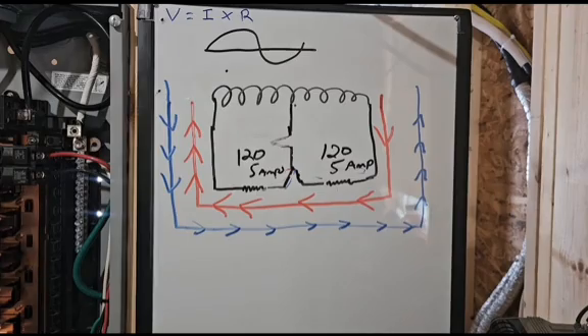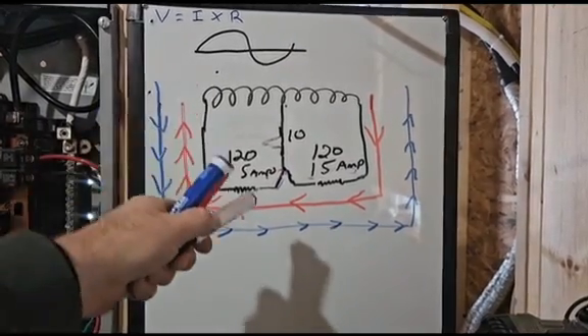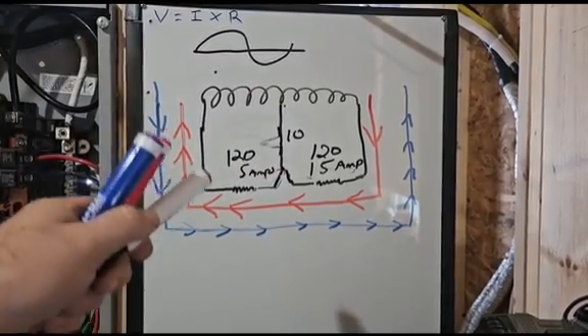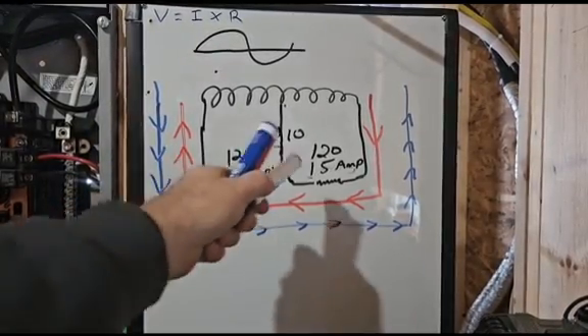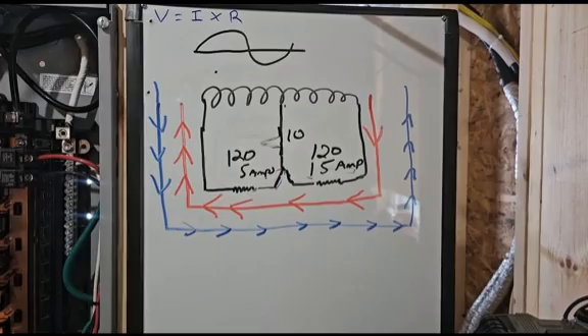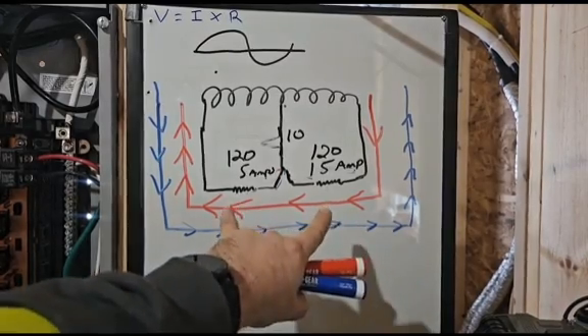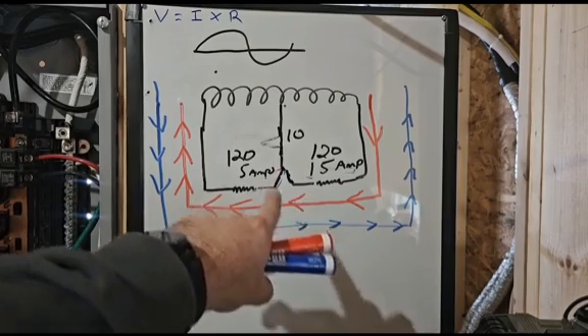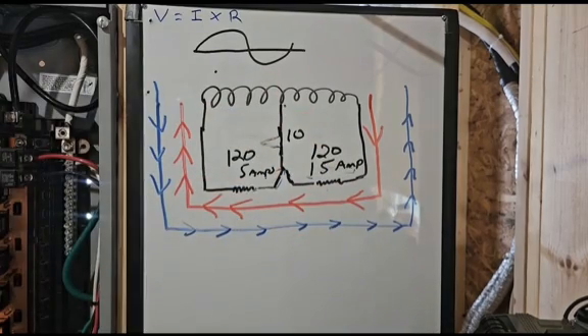But if it is uneven, the neutral, by accepting the extra or providing the extra, allows us to maintain the balance of 120 and 120. The loads are no longer in series on the full 240. The balanced section of them is in series on the full 240, but the imbalance goes back on the neutral.